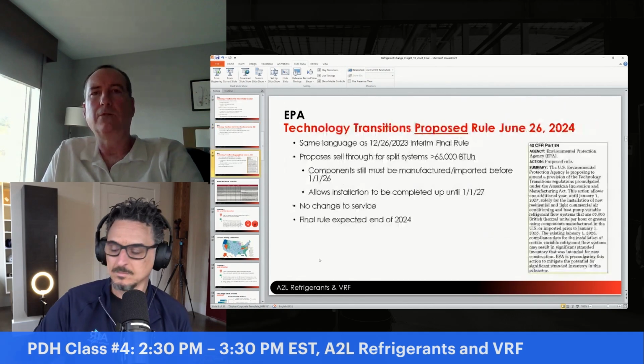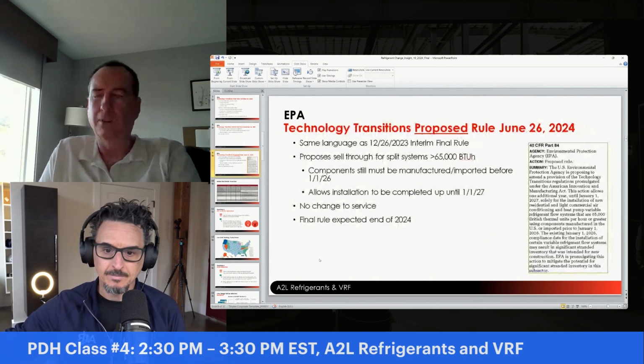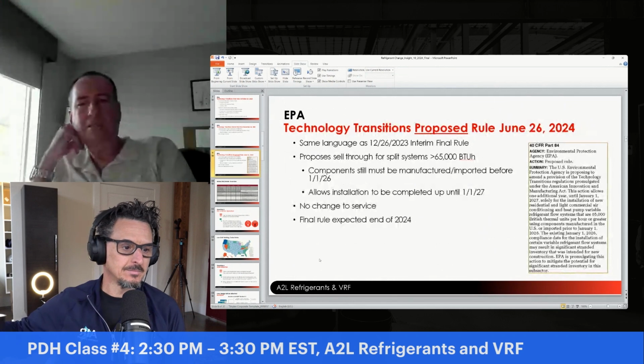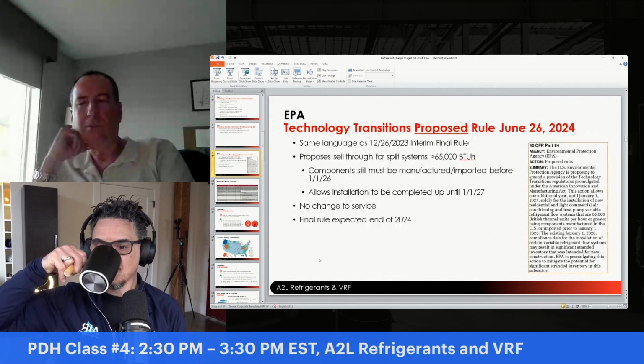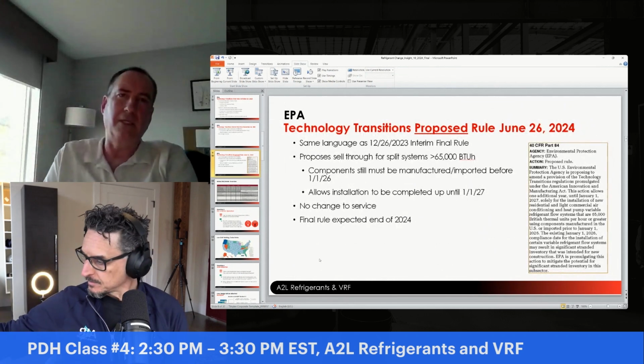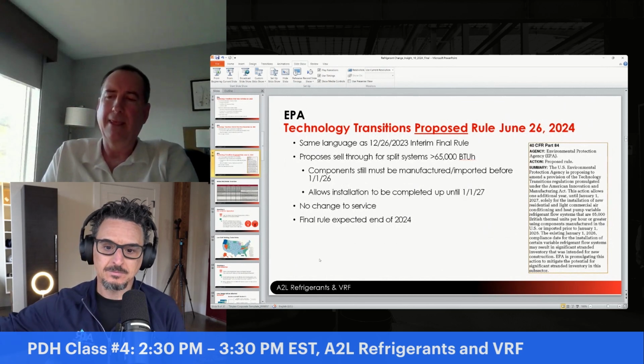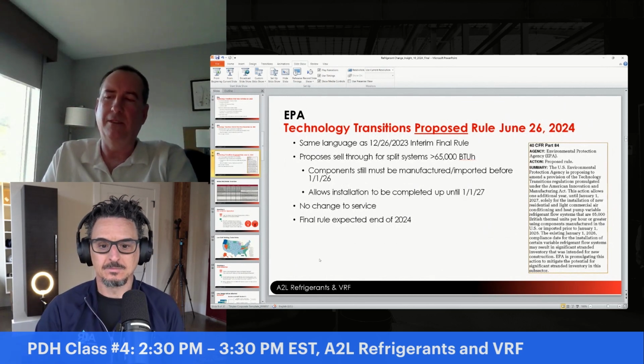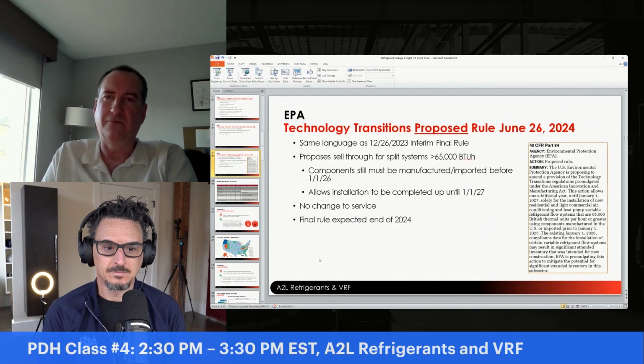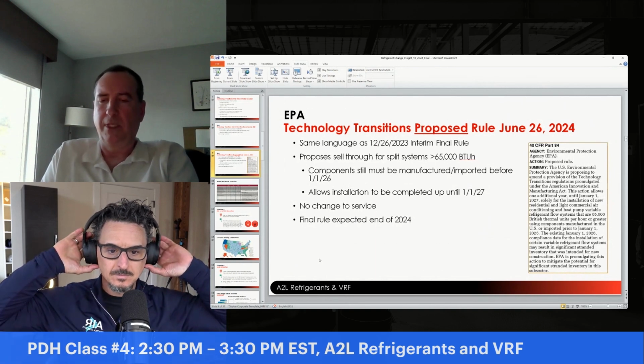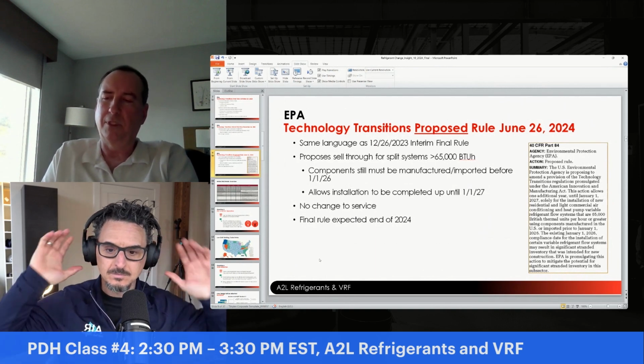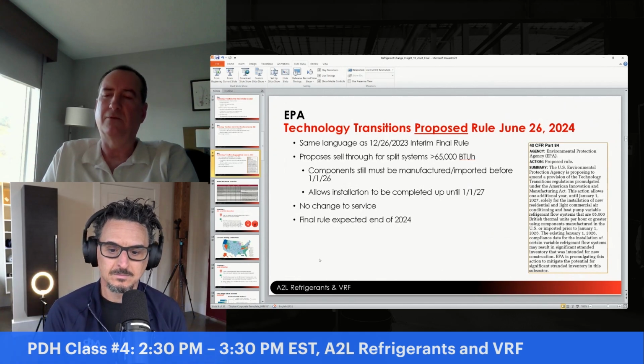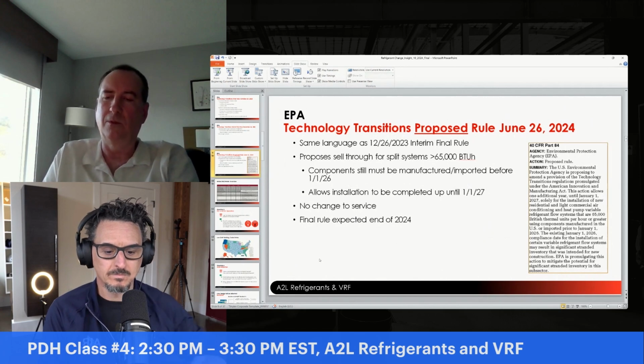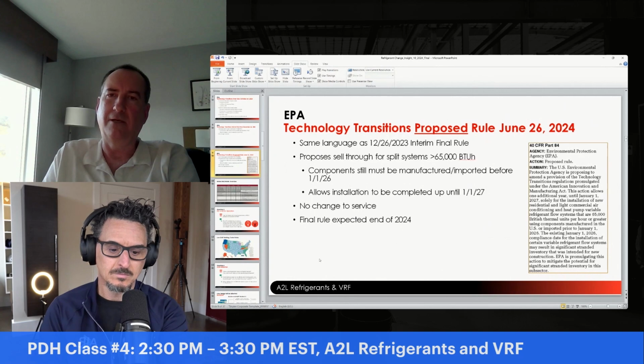There's also a proposed rule we're looking at now, which has the same language as what was in the December 26th interim rule on the previous slide. This proposes a 1-year period to get VRF systems greater than 65,000 BTUh installed after the production/import phase-out dates for new equipment. So components manufactured before 1/1/26 would be able to be installed prior to 1/1/27.